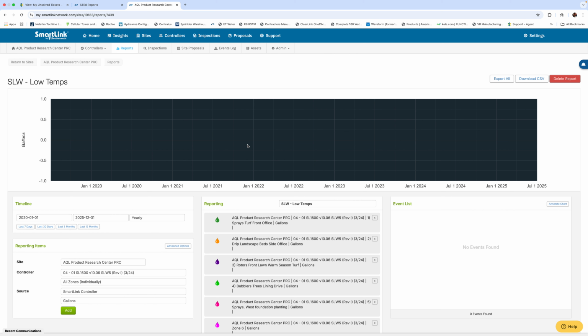then you're going to want to look at our diagnostics videos on how to troubleshoot the air card, the communication cable, or the flow insert itself, how you can test that so that you can figure out why you're not seeing any flow information. But at this point, I would have to say the controller 4-1, the 1600, has never had flow. We've not seen anything from it historically.